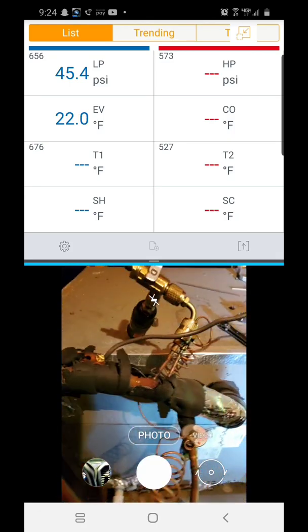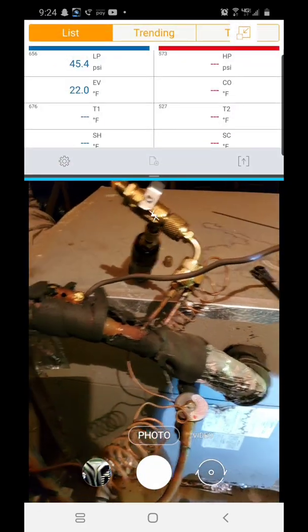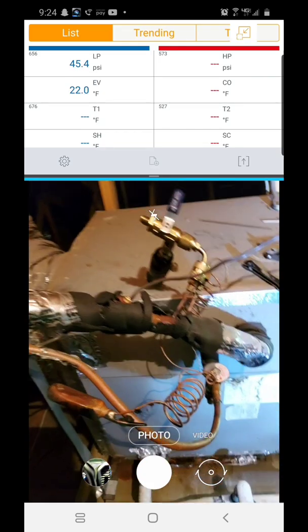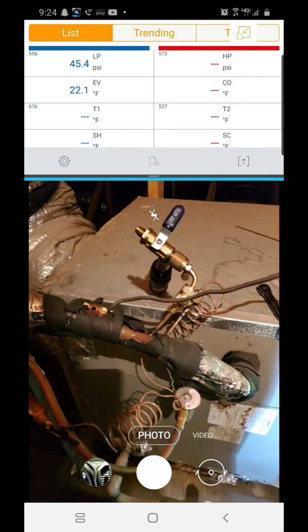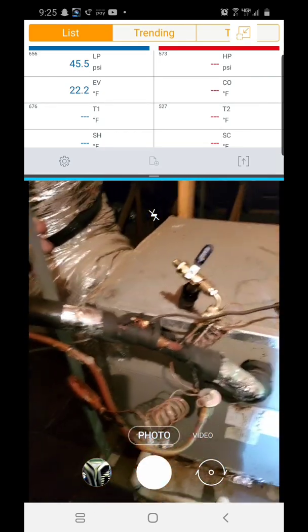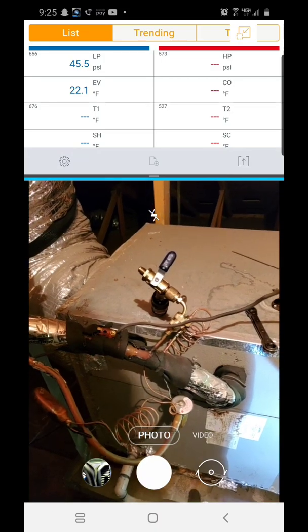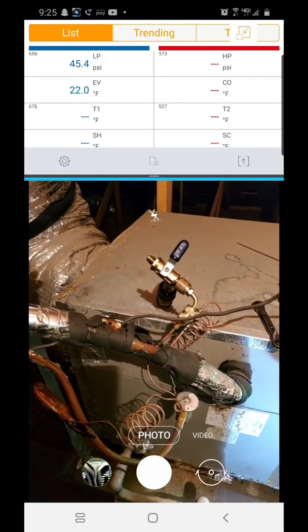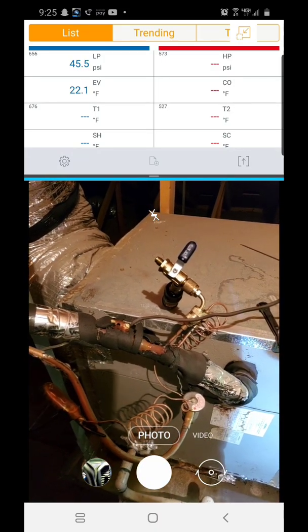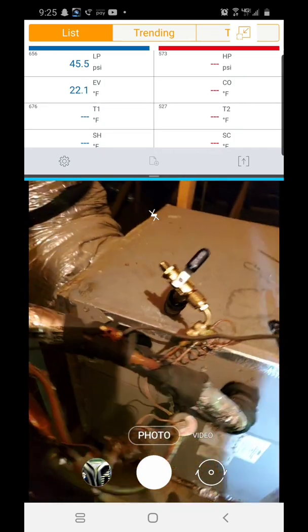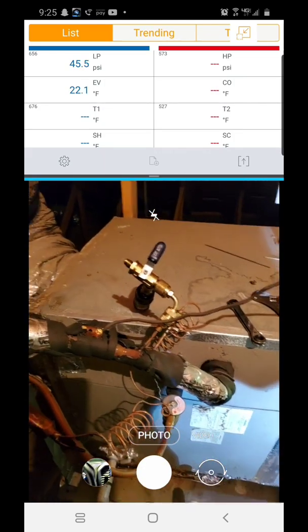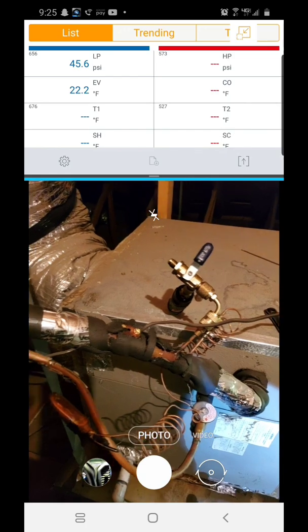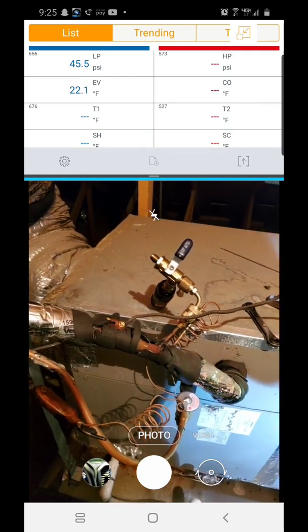So, R22 and my POS Goodman unit. Changed the outdoor fan motor today because I found the compressor totally overheated. It took like over an hour to cool off with water to reset the old reciprocating compressor. It did reset and seemed like it was kind of cooling after I turned it on for a few minutes.